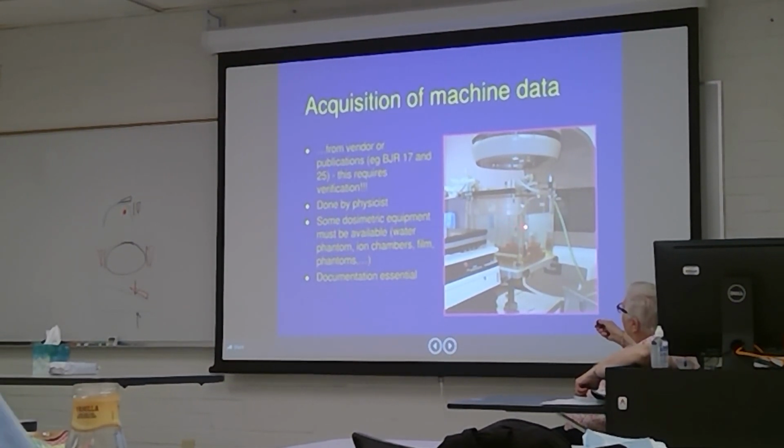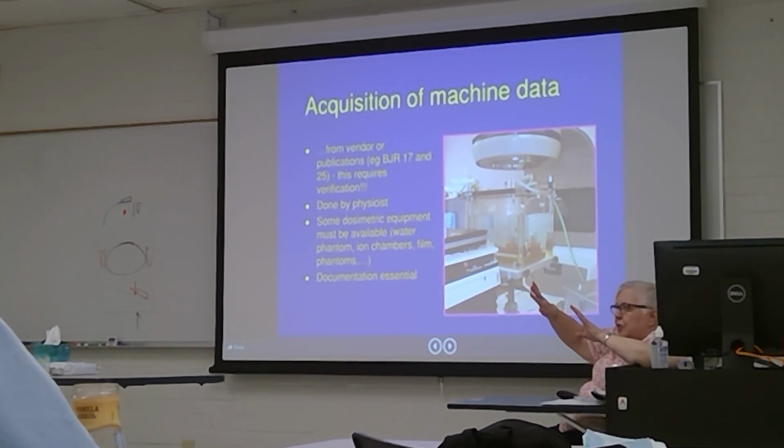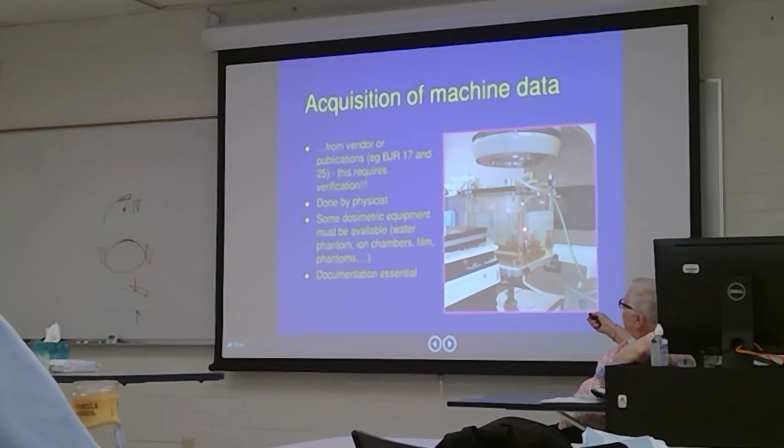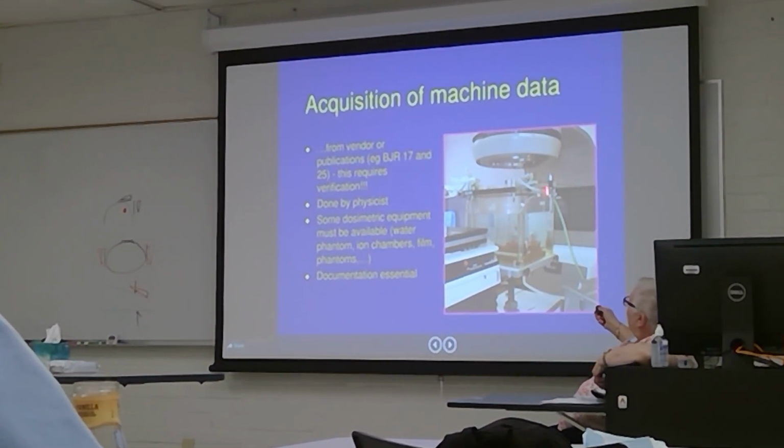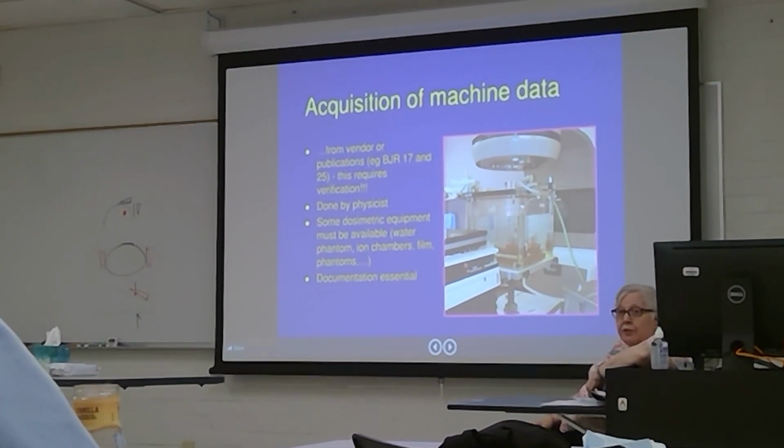What happens is that this is all attached to a piece of equipment outside of the room, and when the machine starts, it actually produces isodose tables or depths. So you want to know what the percentage depth dose is at 10 centimeters. You run a beam, program it, and it'll give you the percentage depth dose at 10 centimeters.